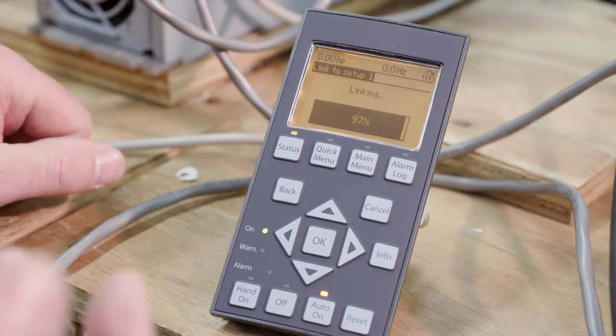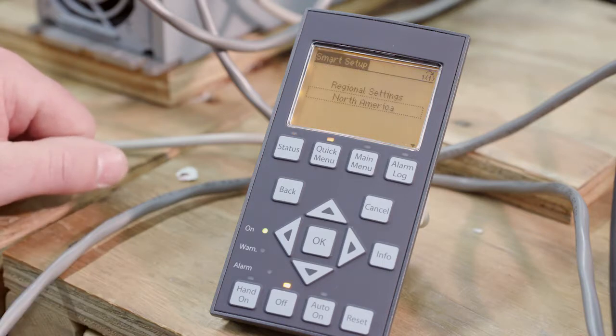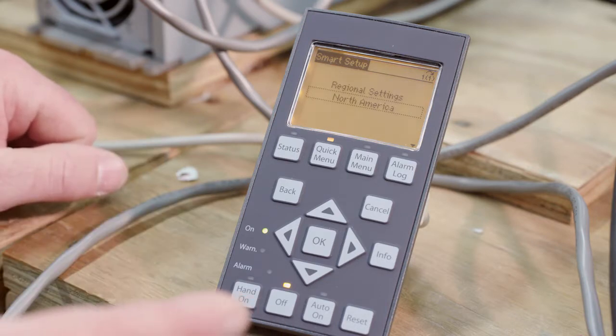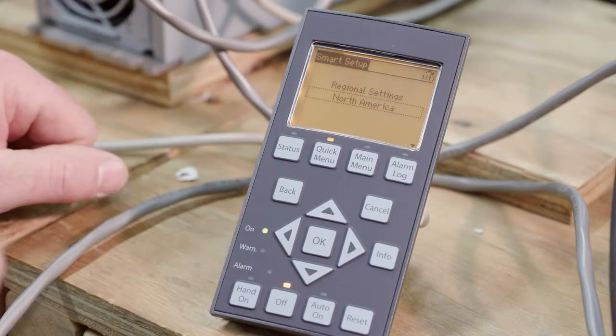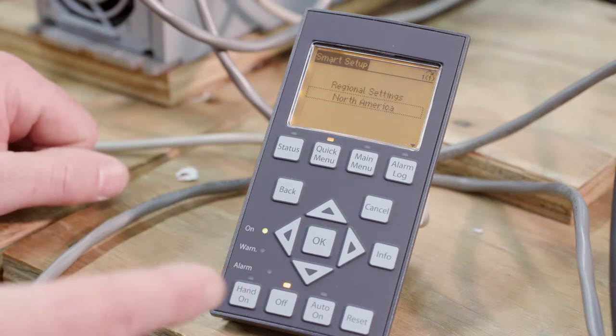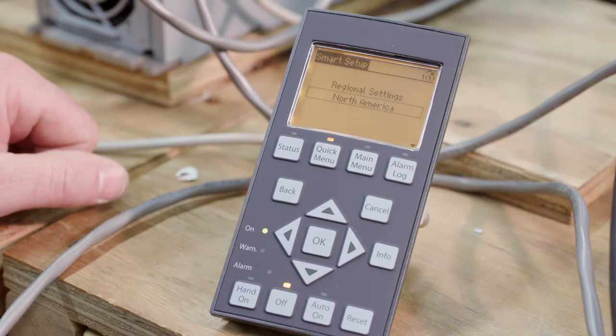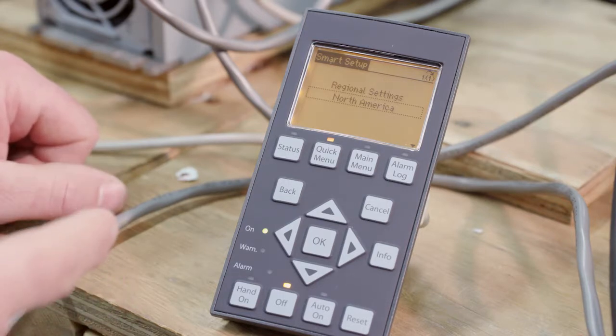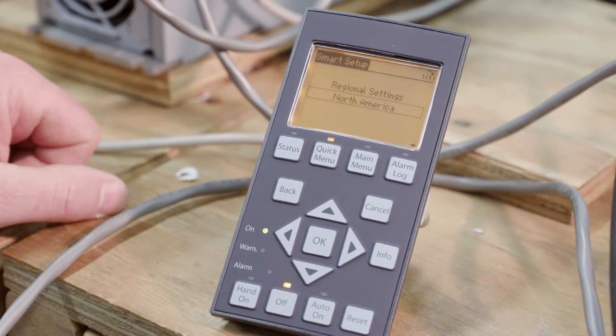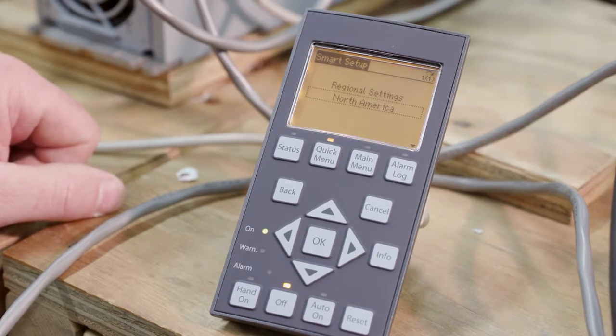So one of the things that you are going to want to do is check rotation. Notice there that it does turn the motor slightly, so you are able to check that rotation at that point in time, and you want to make sure that the rotation is correct. In this case, we're working with some ESVs with the guards off the couplings, so we can see the arrows on the coupling itself. So you always have to check rotation.